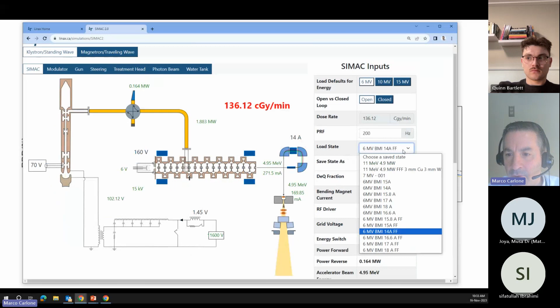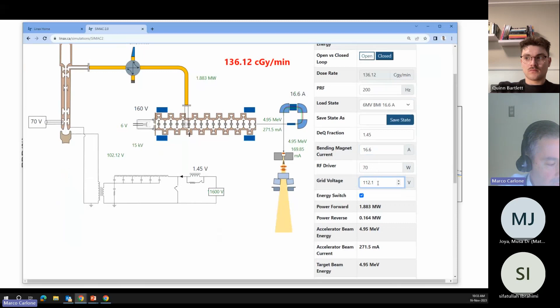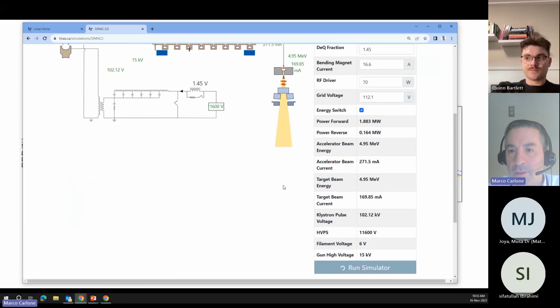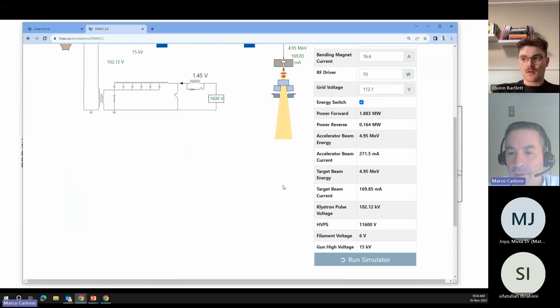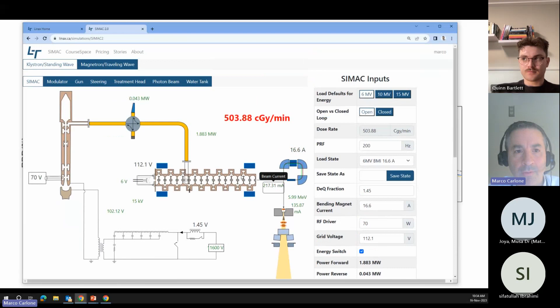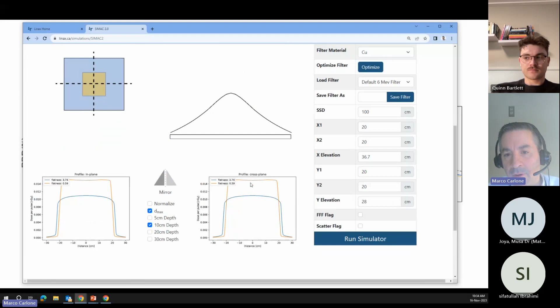And again, I've gone through and done different energies, so I can go back to here. This is the 16.6 amp beam. This is essentially the configuration for a 6 MV beam. So this goes back and we're going to regain the 6 MV beam, which is the one I started with. I can run the simulator to show you that we can recover the same beam that we started with. Let's run. Go back to our treatment head screen now, and oops, that put the flattening filter back in. I'll take that out. So now that's come out, and we've recovered our flat beam.